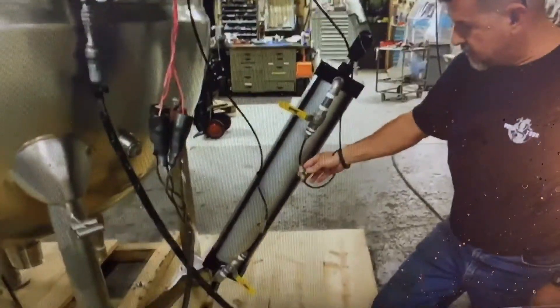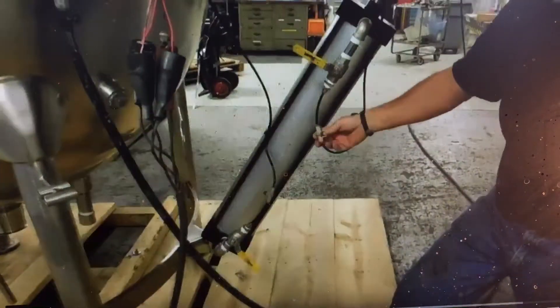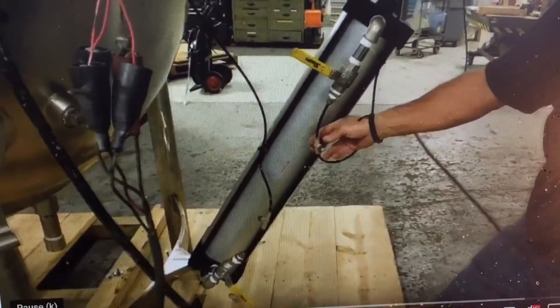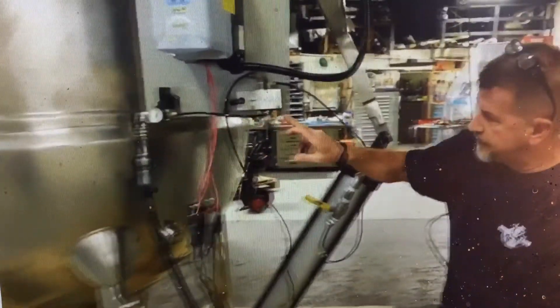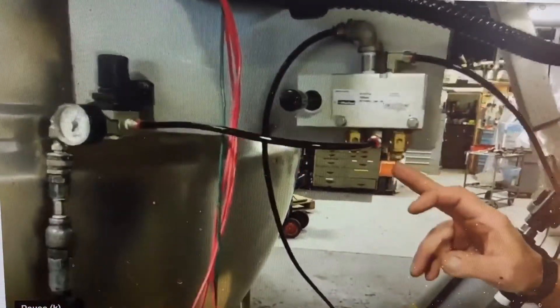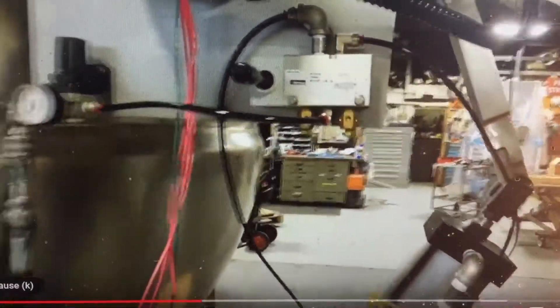Also on the lines here, you'll see these little T's. They have a small throttling device which controls the size of the orifice as air passes through it. Also on the control, these two little brass fixtures right here — you'll hear one is actually venting some air — have an adjustment on the bottom of each one that controls how fast the air goes into the unit.